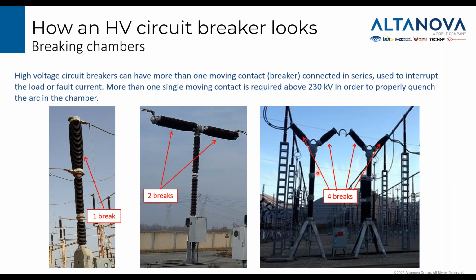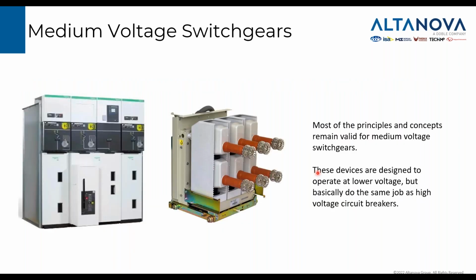According to the rated voltage of the circuit breaker, you may find more than one break per phase. For example, if the voltage is higher than 230 kilovolts, usually you find 2 breaks per phase. In older designs of circuit breakers, you can find more than 2, maybe 4 breaks per phase.